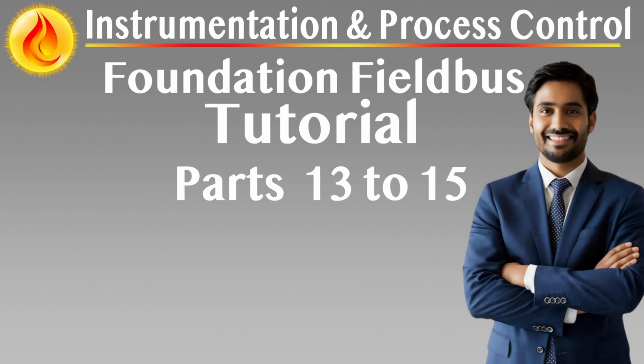Device selection strategy is a key planning task. Engineers must identify Foundation Fieldbus capable instruments that meet both process and communication requirements. This includes evaluating function block types, diagnostics capabilities, power consumption, compliance with IEC 61158 standards, and FieldComm Group registration. For standardization and maintenance efficiency, the project should limit the number of device types and vendors while ensuring interoperability across the system.